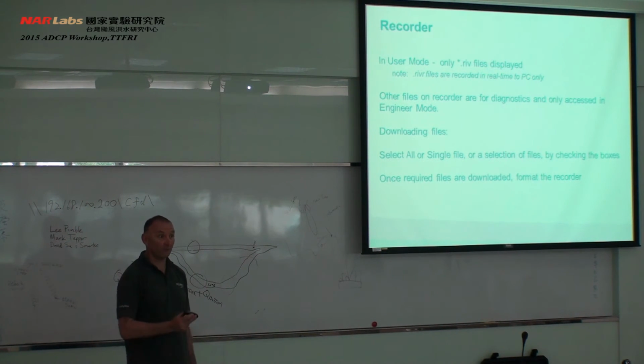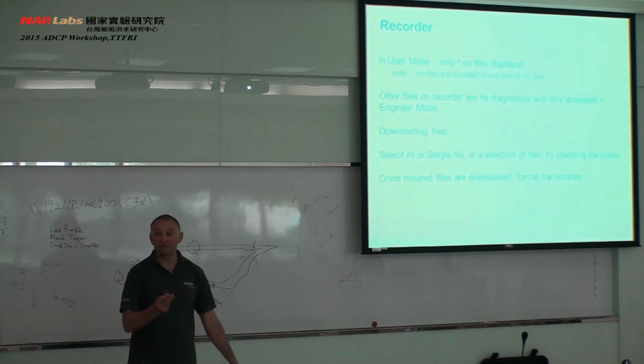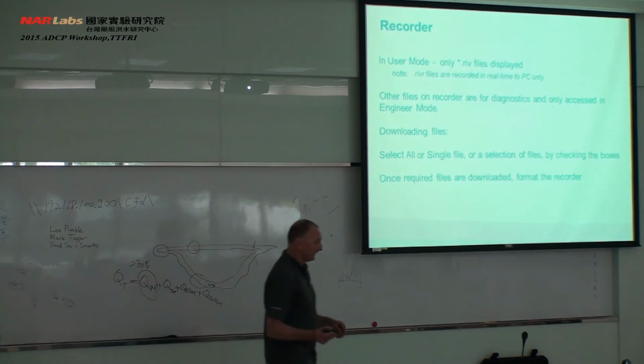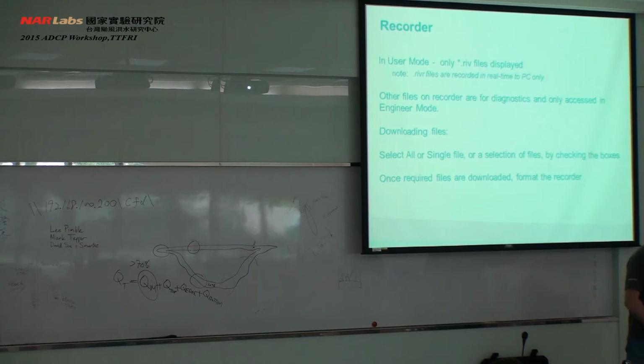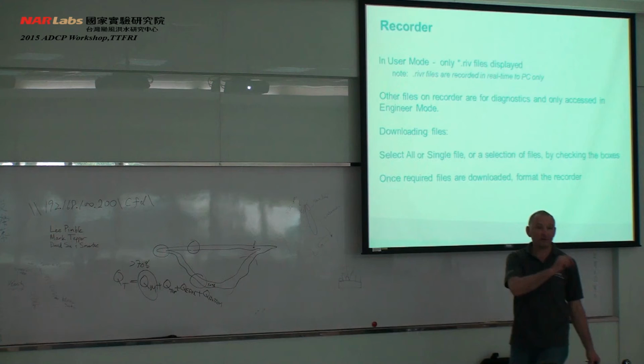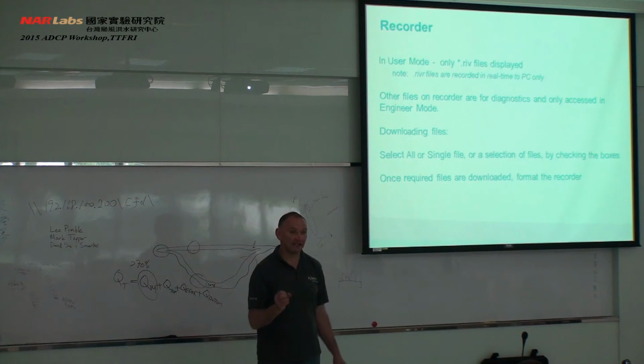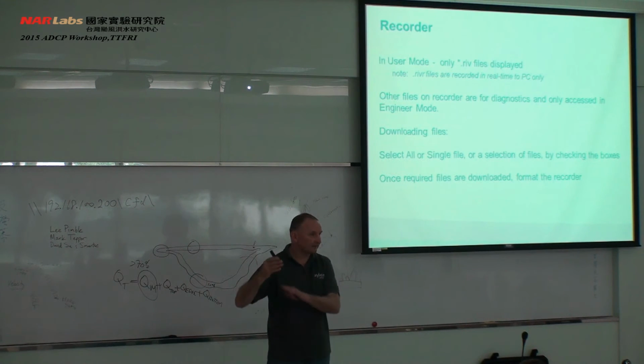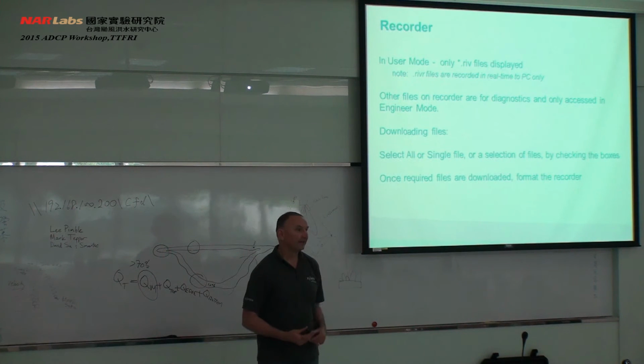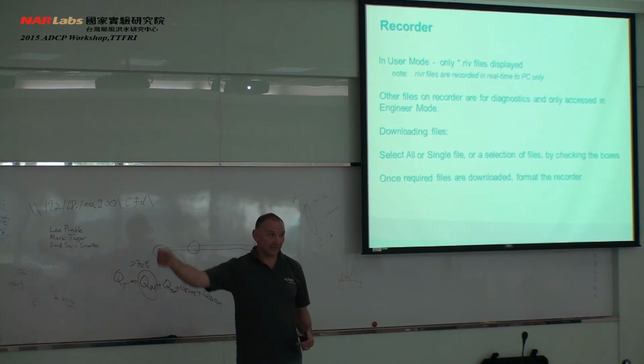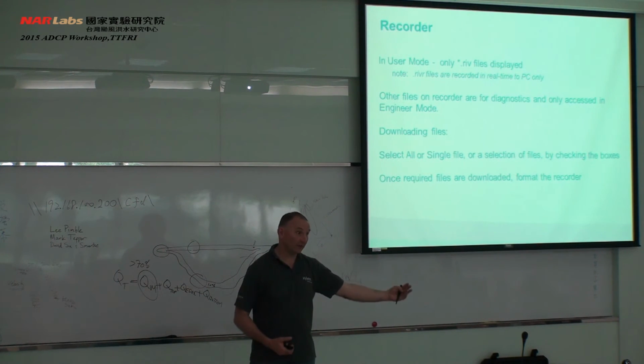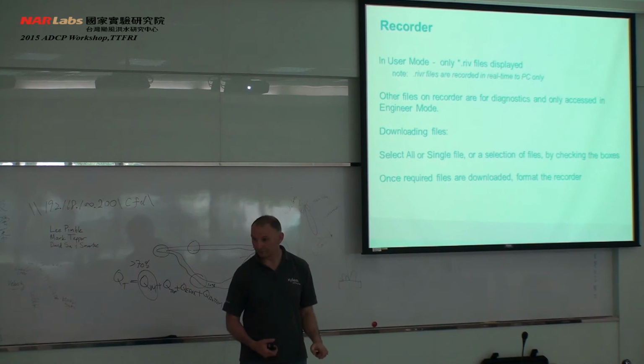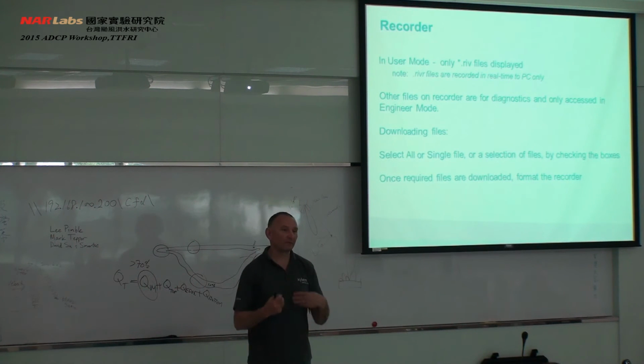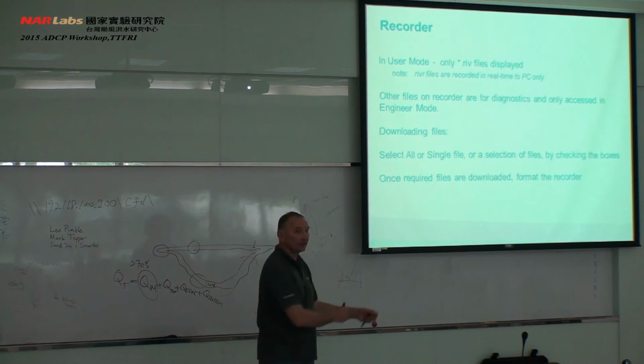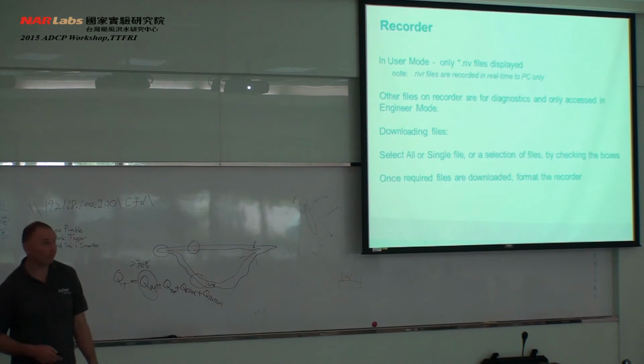That file, although it has missing samples, is actually still usable as a river discharge measurement file, as long as you had communication with the instrument when you stopped the measurement. Because every 1 second, as well as sending all of the data, the instrument is also sending a summary to the PC. And that summary has the key things like distance, depth, velocity, discharge. So although the file is missing some data, the actual discharge value at the end is still correct and usable. But I would recommend that for that one, you go back to the instrument and download the .riv file. That's what I certainly recommend.